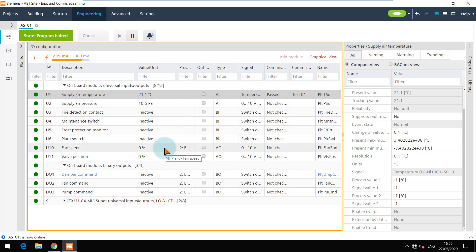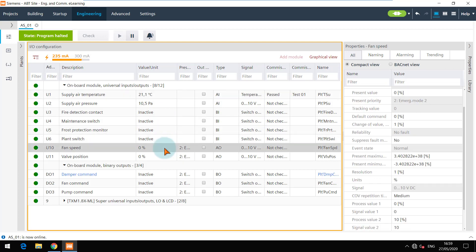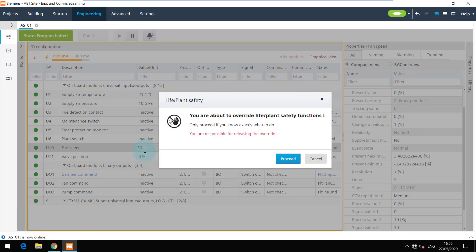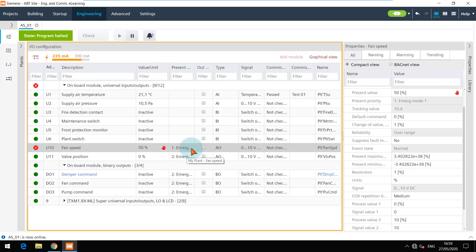When the state of the device is program halted, all the outputs are commanded with priority 2, and the value of the output is what is set in the backup mode in the BACnet properties. To override the output we need a higher priority, and hence this warning message is shown. To test this data point we can proceed with the warning.